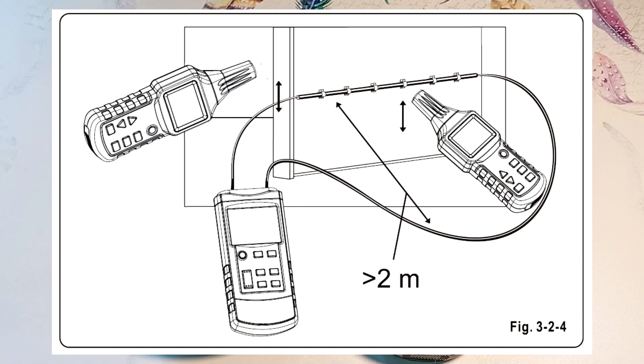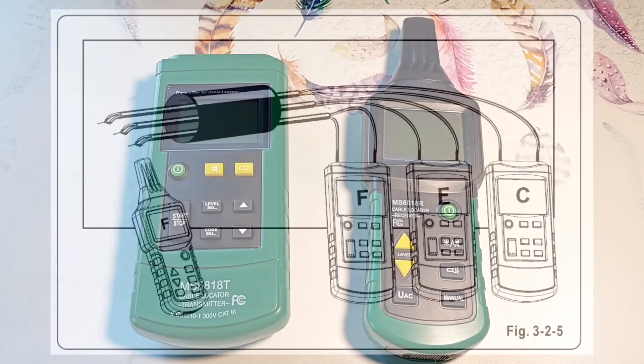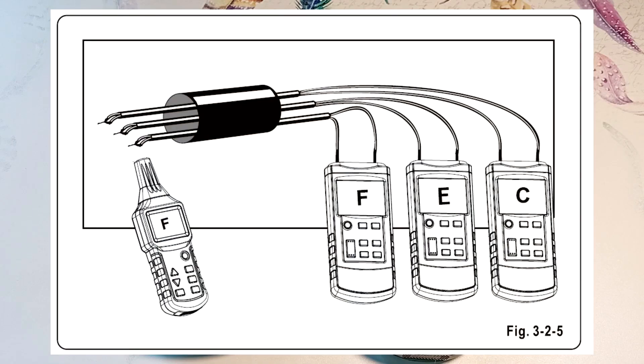This figure shows the detection of deep wires. The circuit must be de-energized. The generator is connected to the two ends of the wire located in the wall. It should be taken into account that the distance of the loop wire to the wall should be more than 2 meters. It also shows the detection of several circuits at the same time, or the distribution of a three phase circuit.